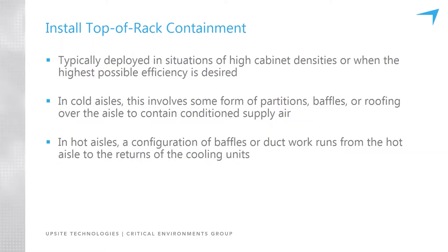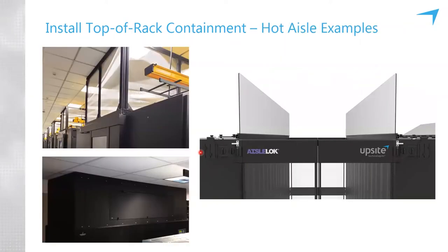Top-of-rack containment is also potentially very important for other room layouts where there may be a low ceiling and cooling units on opposing walls, causing exhaust air from a hot aisle to flow over the top of a cold aisle to get back to the cooling units. Containment solutions will always provide some improvement and enable further reduction of fan speeds and potentially raising cooling unit set points to further optimize the room.